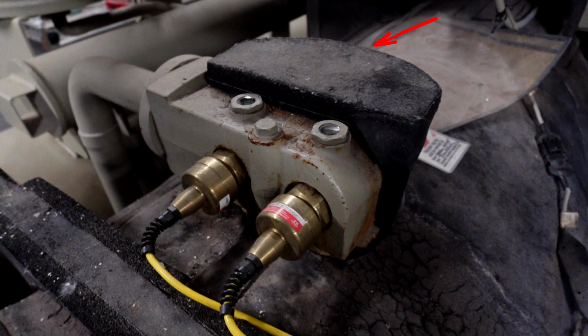Now, when these begin to scale into a much larger size, we can start getting into these valve blocks. These valve blocks are quite literally just that. We have an entire block of, this would be like a cast iron block that's been machined, and our liquid line is coming up here into the side. And essentially, instead of using one massive and extremely expensive EXV to control the flow here, we can go with a double stack, and you can stack these valves. Essentially this is ported in such a way that the liquid is sent into this block and then it's routed through each of these valves internally through internal porting.